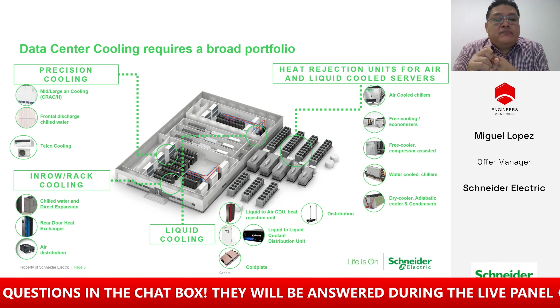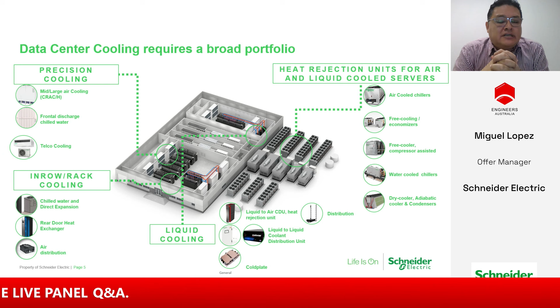Those are available. Bottom left of the quadrant, you see your in-row rack cooling systems. The reason I'm talking about air conditioning is that these will form what's called supplemental cooling for your liquid-cooled system. As I'll explain shortly, we will still need to be deploying either precision cooling, CRACs, CRAHs, fan walls, or in-row coolers. There's also been an acquisition by Schneider of a company called Motivair, which now opens the door to so-called rear door heat exchangers.